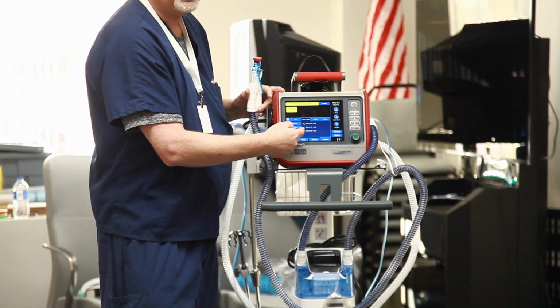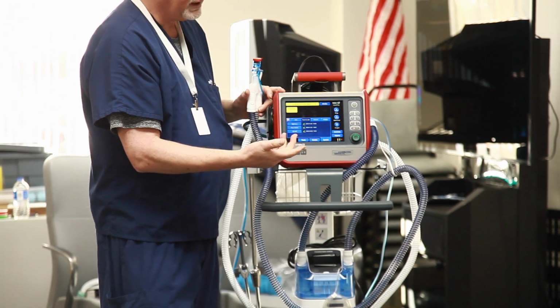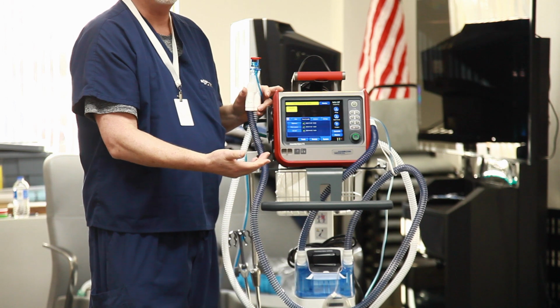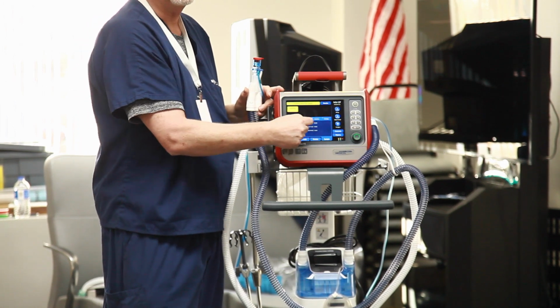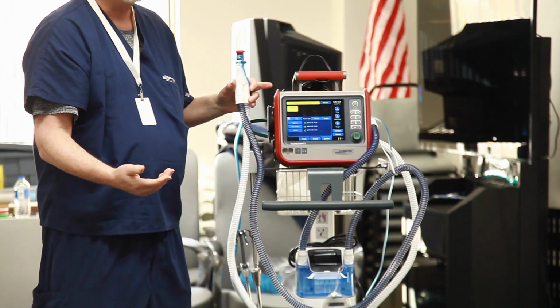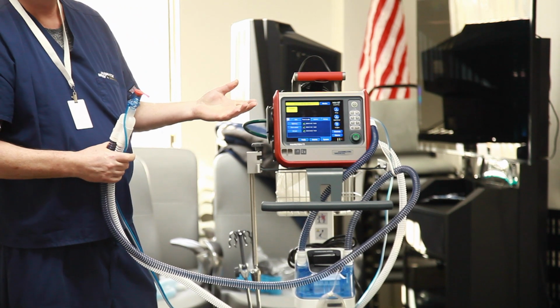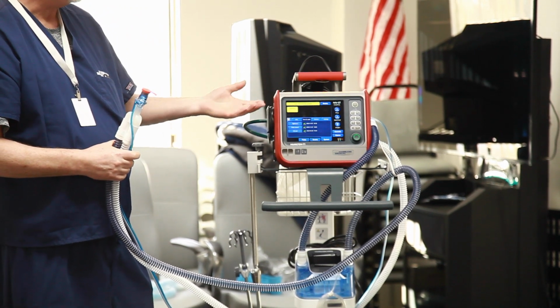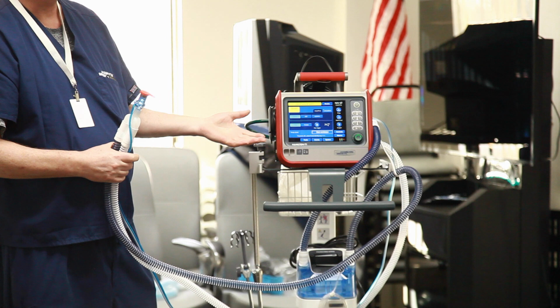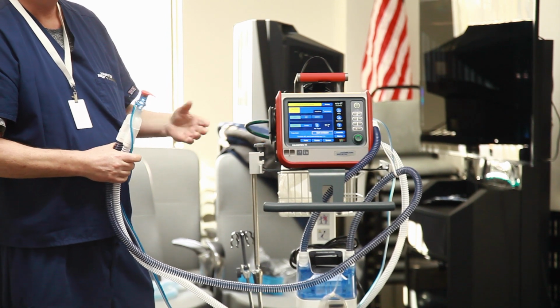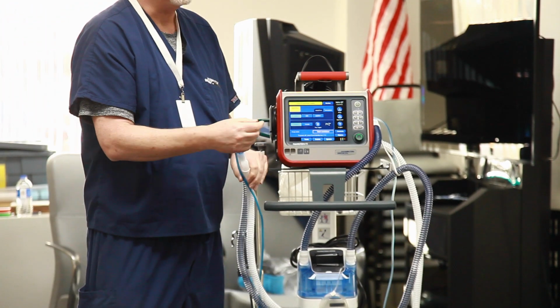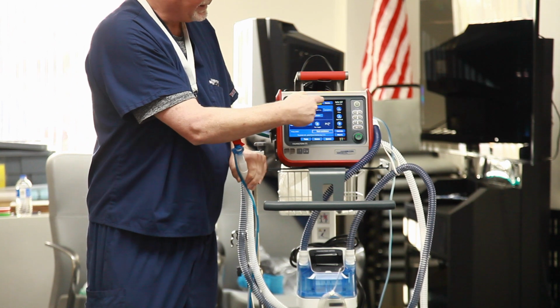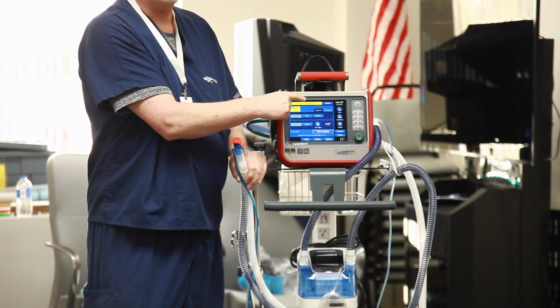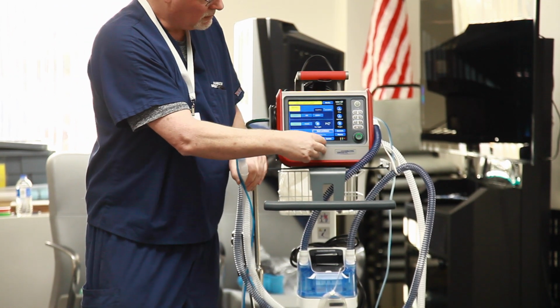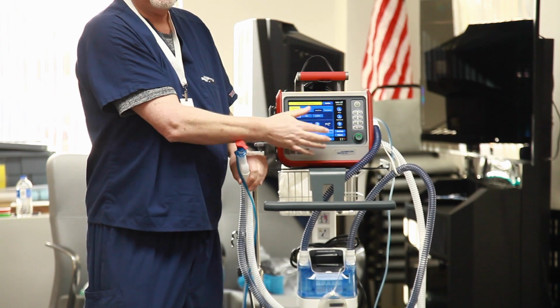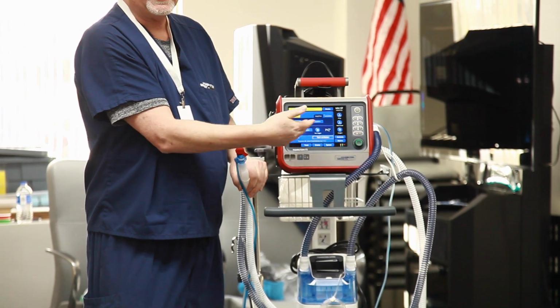If there's a red X there, just hit O2 cell and calibrate. It's going to take about 2 minutes. There's a little timer here, and when it's done, it's done. It'll calibrate to whatever you're plugged into. Right now, I'm not plugged into anything. It's going to calibrate to room air. If it's running on a patient, and I get an alarm here that says calibrate O2 sensor, I don't have this standby screen right now because it's actually running, right?